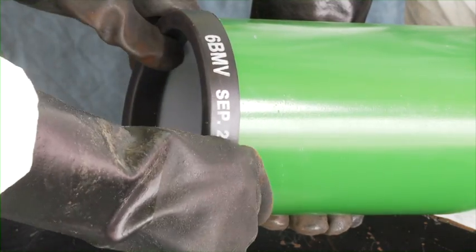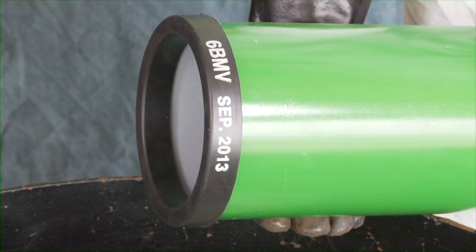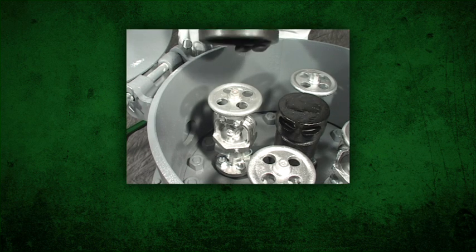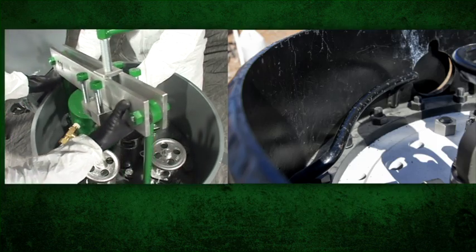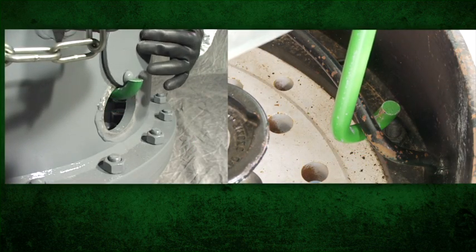Place gasket 6BMV on Hood 6A1. When ambient temperatures are low, it is desirable to perform this task in advance, preferably in a heated area. Also, the bottom edge of the hood should be smooth — nicks, cuts, or an uneven edge can prevent the hood from sealing against the pressure plate. Place Hood 6A1 with gasket 6BMV over the leaking valve. Do not obstruct the hood vent valve outlet as access may be required later. Place the yoke assembly 11A hooks into the port openings of the protective housing, or to the mounting bars inside the housing if provided.